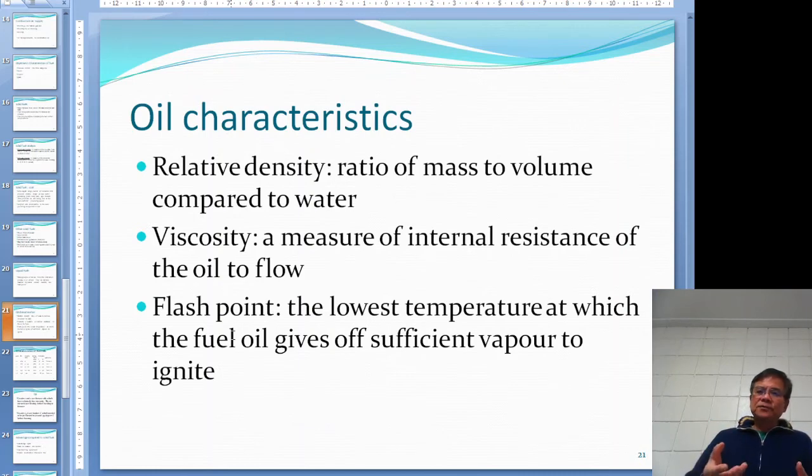Now one of the methods used in North America measures 60 cubic centimeters of a certain amount of oil, and lets it flow through a filter. They count the time, the seconds it takes for every drop to go through. This one is SSU, the Saybolt Universal Unit or something like that. So the thinner oil will go through the filter in no time. The heavier oil, with higher viscosity, takes longer to flow. So if the viscosity in SSU is lower, that means it's lighter, not that thick.